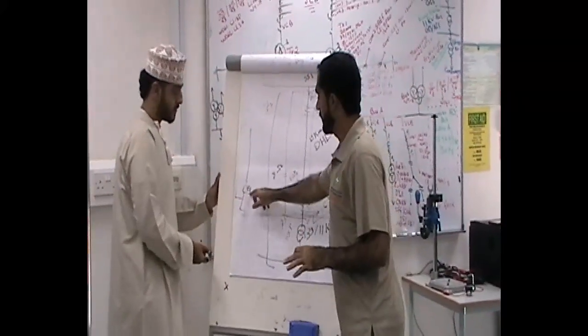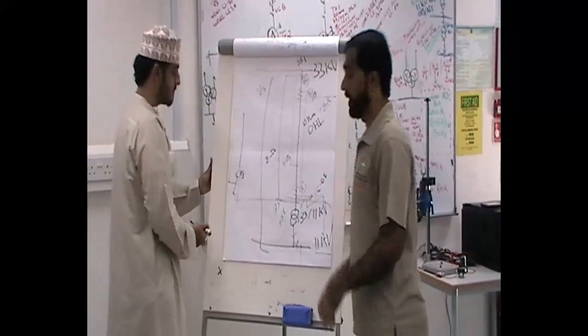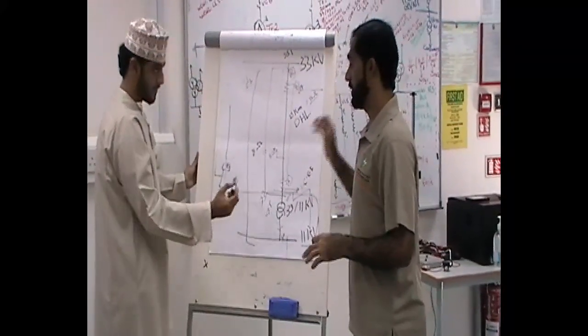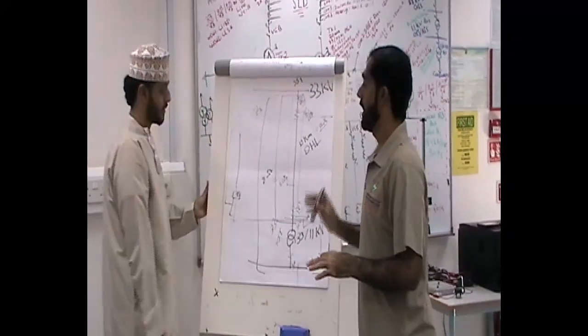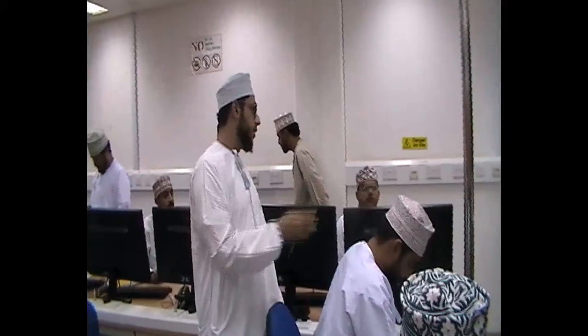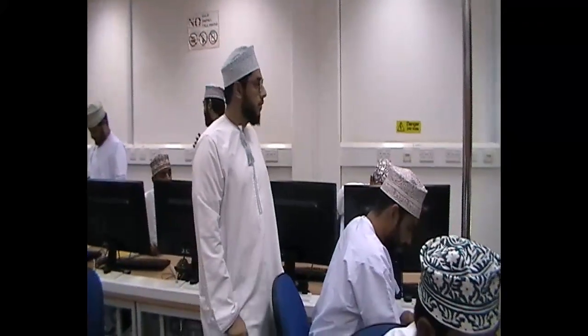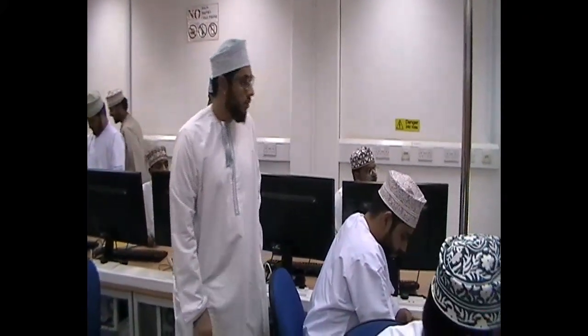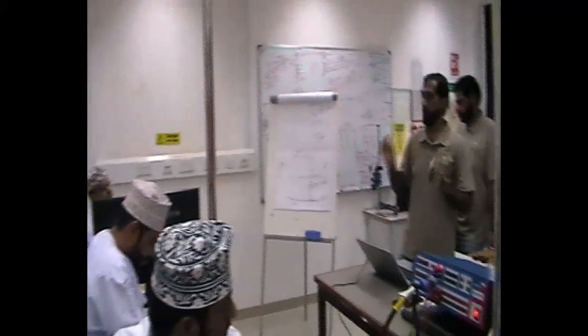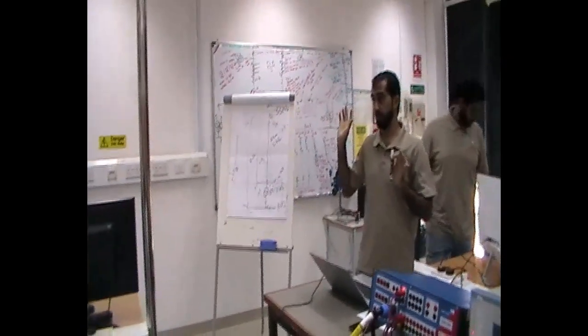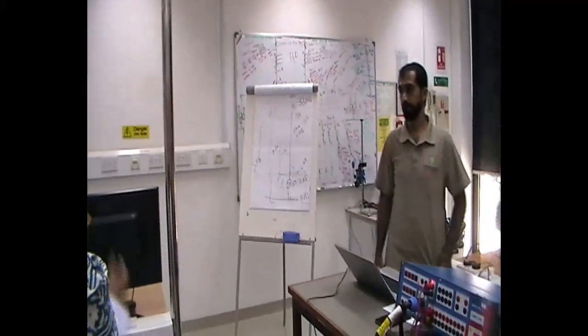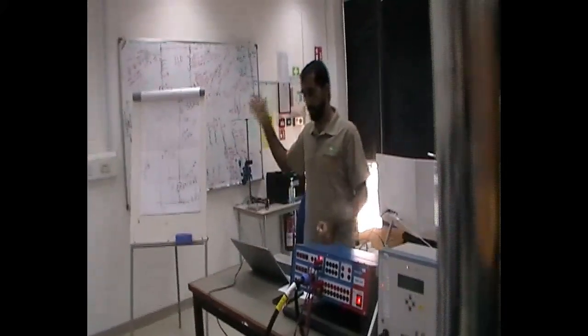The nearest relay to the fault should operate. It's always all-time protection. The nearest relay should operate. If not, then the backup. Zone 1 is the main relay. It's one relay, again, multifunction, but zone 1 is what I'm expecting as main protection. The rest is backup. Plus I have overcurrent backup.